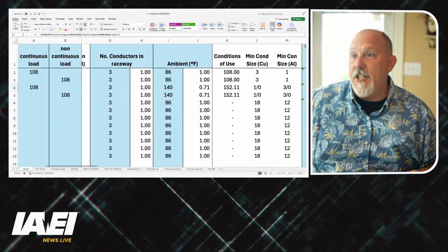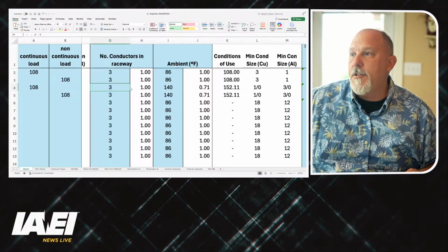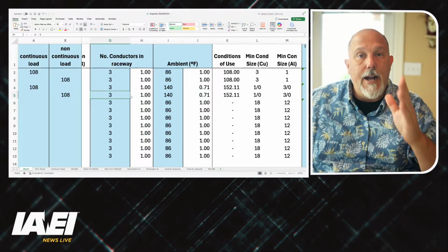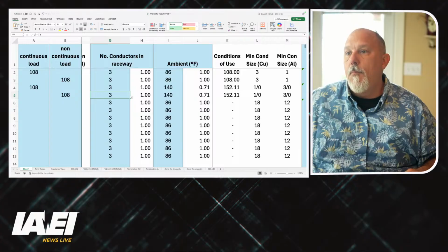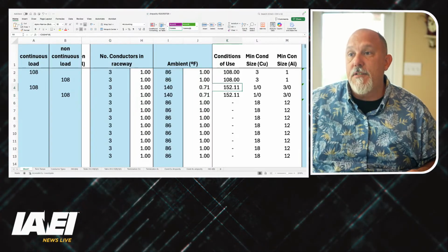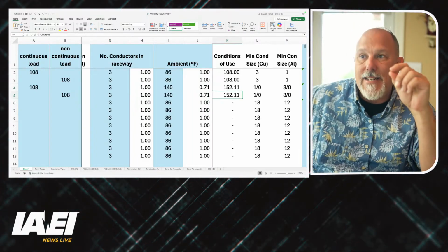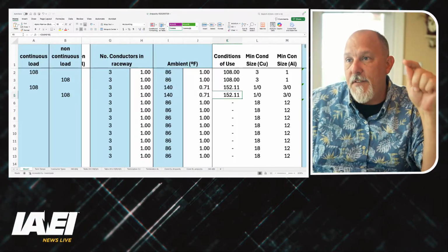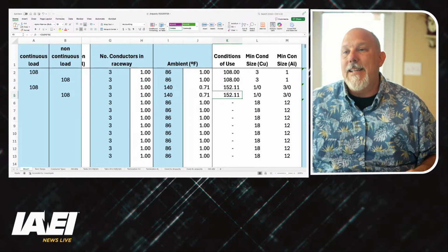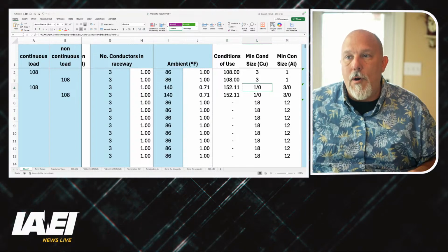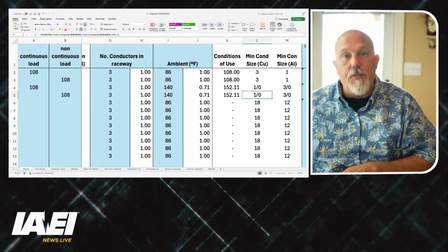Now we get to the conditions of use. 3 conductors, it's unity, elevated ambient temperature, 0.71. So now based on my conditions of use, my ampacity has to be greater than or equal to 152.11. To get that done in copper, a 1 aught will satisfy both conditions.